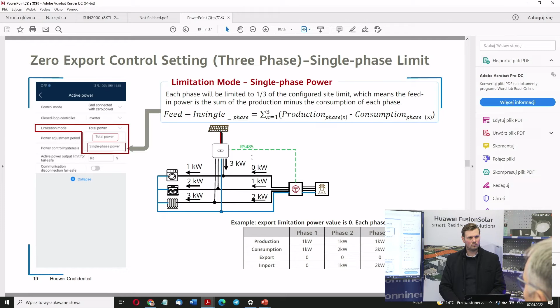But here's the question — can this be adjusted somehow, like the smart meter taking into account all three phases together? I don't want a situation where my client, or say the energy company, claims I sold more than 100 kilowatts somehow. It needs to account for all three phases so that the power I sell never exceeds 100 kilowatts at any time.